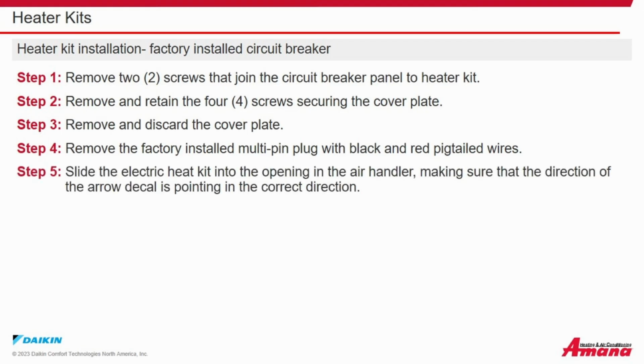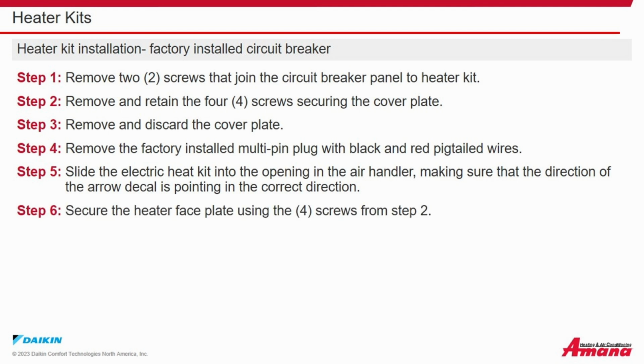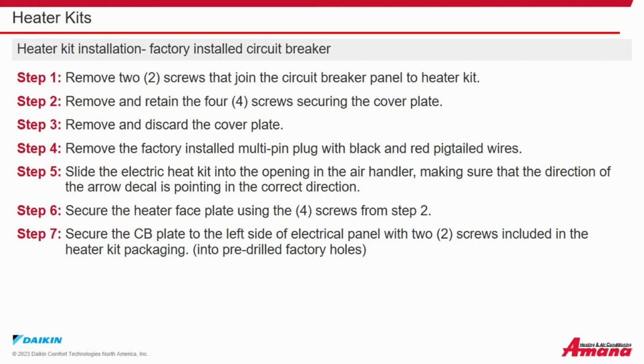Step 5. Slide the electric heater kit into the opening in the air handler, making sure that the direction of the arrow decal is pointing toward the correct direction of airflow. Step 6. Secure the heater faceplate using the 4 screws from Step 2. Step 7. Secure the circuit breaker plate to the left side of the electrical panel with the 2 screws included in the heater kit packaging into the pre-drilled factory holes.